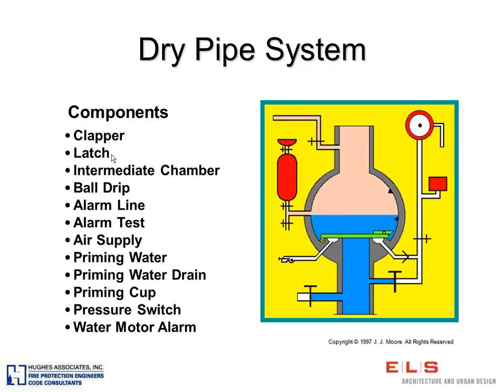So here's a better diagram. We're not going to go through each of these, but quite frankly, I couldn't figure out how to separate the two, so I have it on here. But I like this slide because it depicts what happens in the dry pipe system. This is a valve that's closed, and there's water that's sitting here under the valve with a little bit of priming water on top, and then everything that is in this neutral skin color, peach color, is all air, and there's air under pressure.